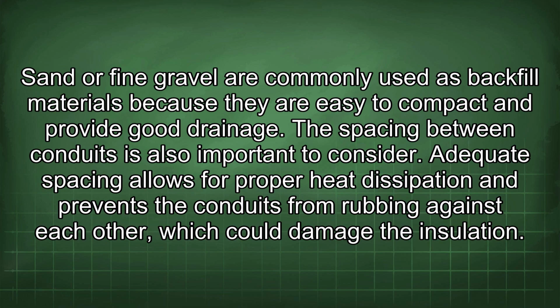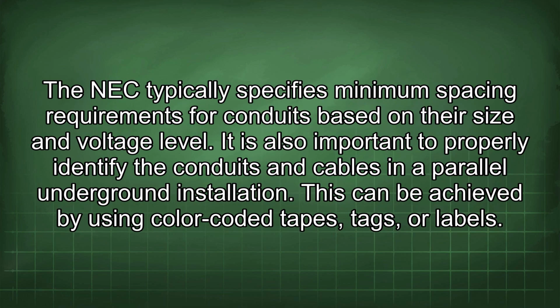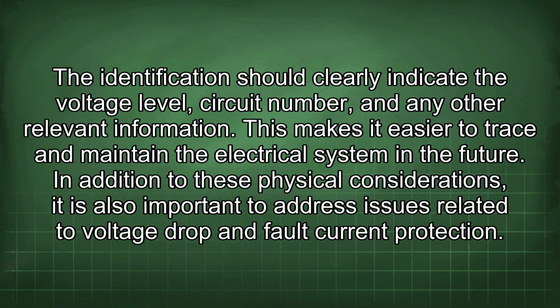Adequate spacing allows for proper heat dissipation and prevents the conduits from rubbing against each other, which could damage the insulation. The NEC typically specifies minimum spacing requirements for conduits based on their size and voltage level. It is also important to properly identify the conduits and cables in a parallel underground installation. This can be achieved by using color-coded tapes, tags, or labels. The identification should clearly indicate the voltage level, circuit number, and any other relevant information. This makes it easier to trace and maintain the electrical system in the future.